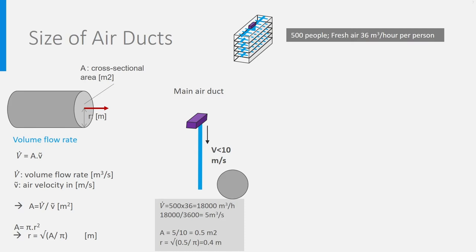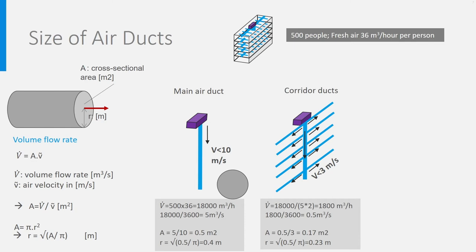Let's look now at the corridor ducts. There are five floors. Each floor needs 18,000 divided by 5 is 3,600 cubic meters per hour. This is divided into two zones, one part of the air goes left and the other one right. So, we need only half per branch, which is 1,800 cubic meters per hour, which is 0.5 cubic meter per second. With an air velocity of 3 meters per second, this leads to a cross-sectional area of 0.17 square meter, corresponding to a radius of 0.23 meter, a diameter of 46 centimeter.